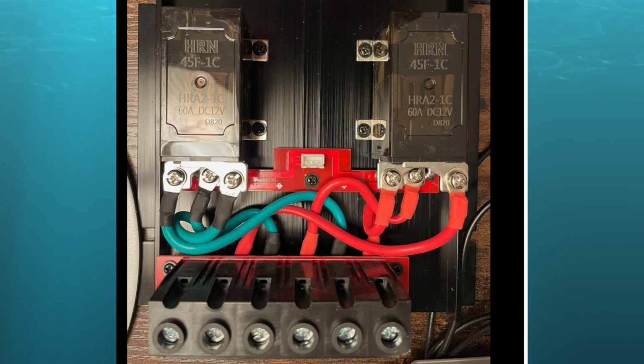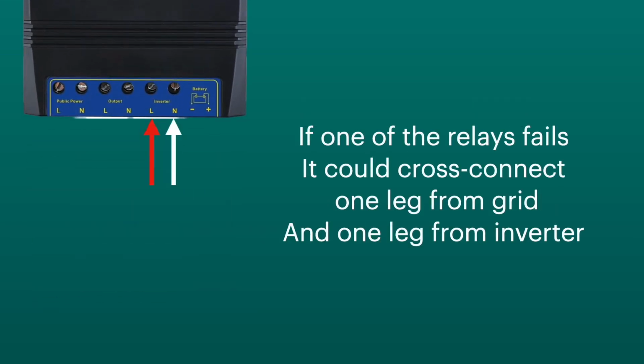Both of these are normally closed relays and they default to the grid. So when the power's off, or even if the battery is not connected, they default to the grid connection. So say the relay that's controlling the line 1 input were to fail, it would default over to the grid input. But your other relay that's running the neutral inputs or the line 2 inputs, this would still be coming off the inverter. So you have one leg coming from the inverter, one leg coming from the grid.